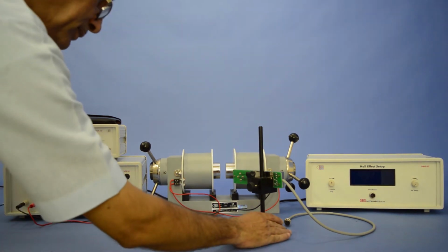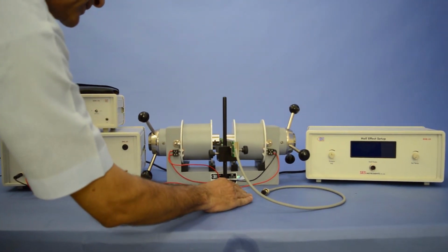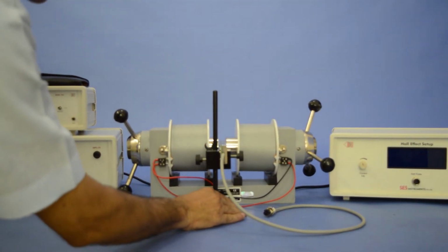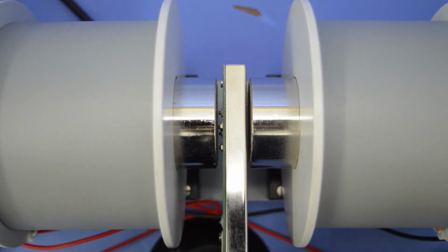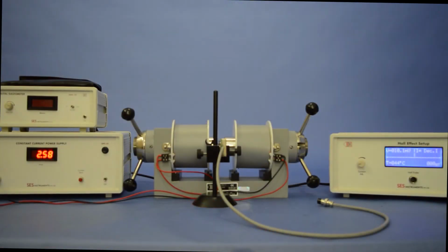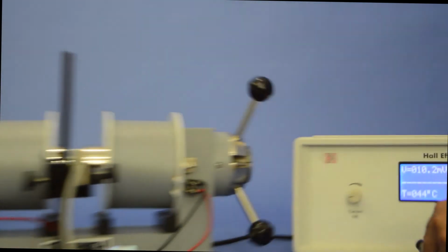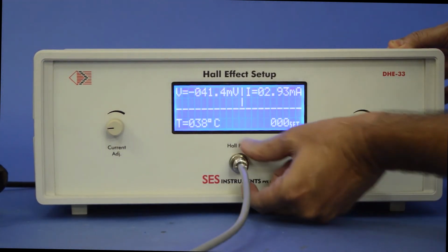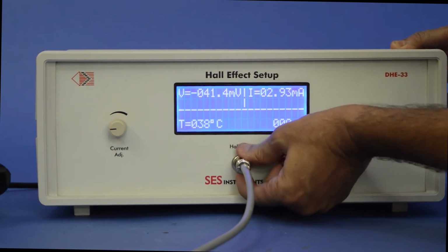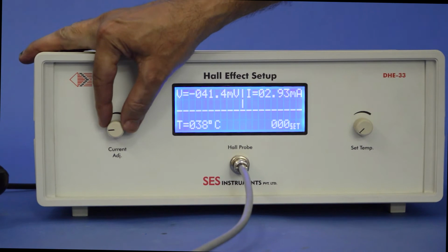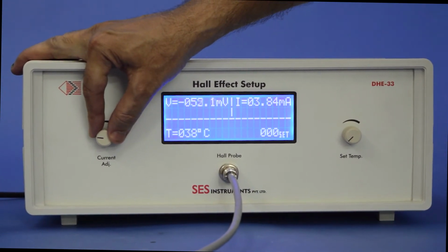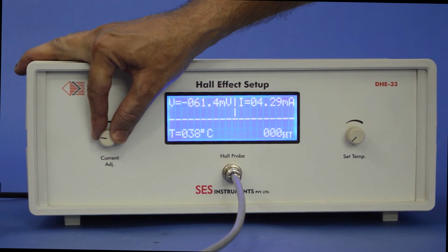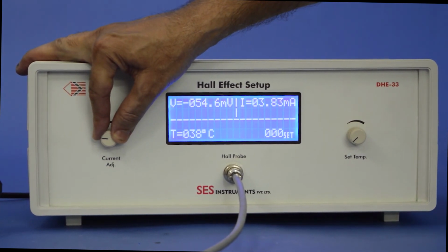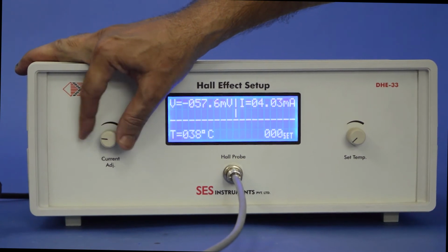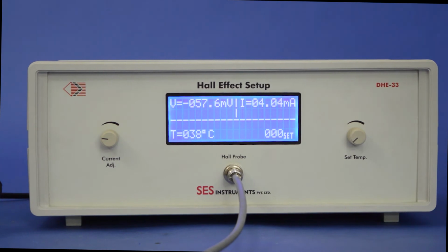Now, place the DHE33 probe between the pre-adjusted air gap of the electromagnet. Keep the probe sample near the center of the poles. Now, connect the 8-pin connector of the Hall probe with the unit and set the current, say 4 milliampere. And note down the Hall voltage at ambient temperature.